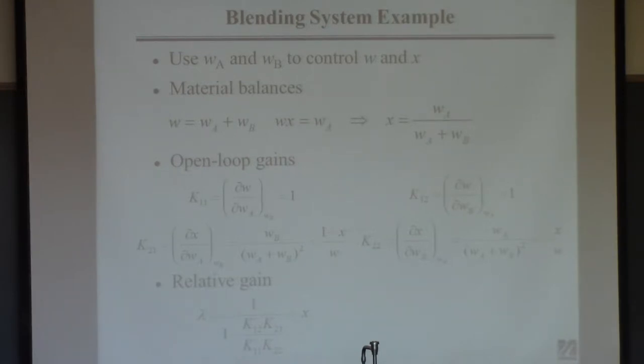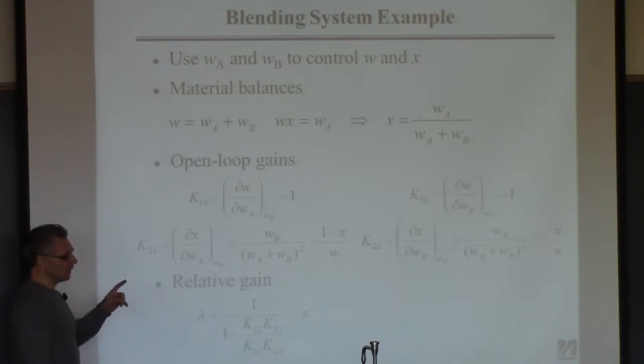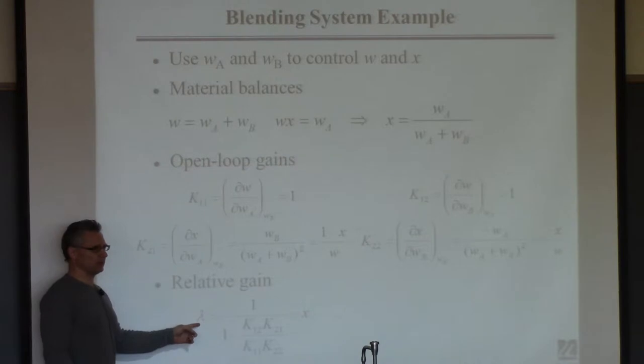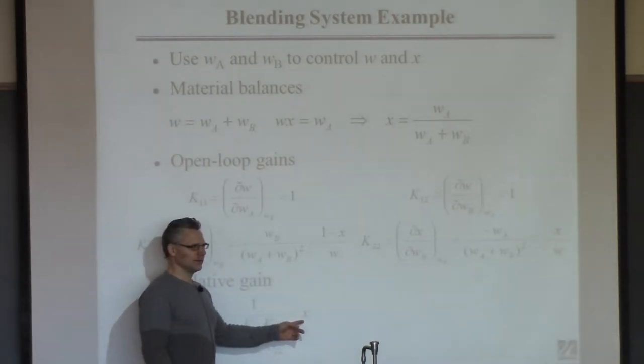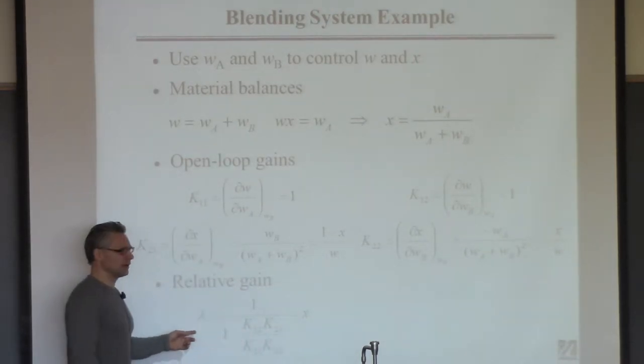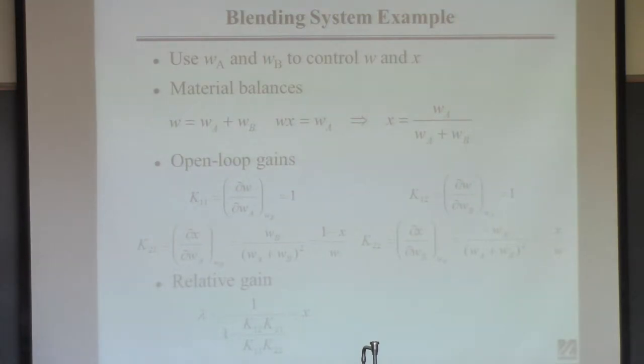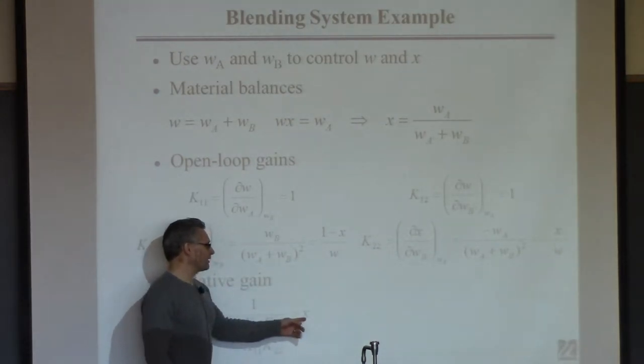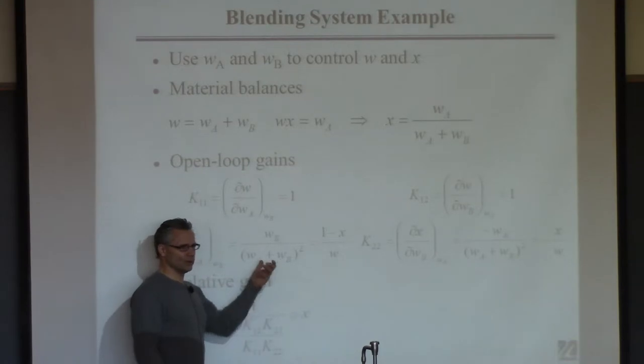What does that tell you? If you want to use WA to control W and WB to control X — pairing U1 and Y1 and U2 and Y2 — this lambda should be close to 1. Is it close to 1? It depends on the mole fraction you're trying to achieve. If you're trying to achieve a mole fraction with a lot of A, that will be a high number like 0.8 or 0.9, and that will be a good pairing. Otherwise, you should use the other pairing. It depends on the actual mole fraction you're trying to achieve.